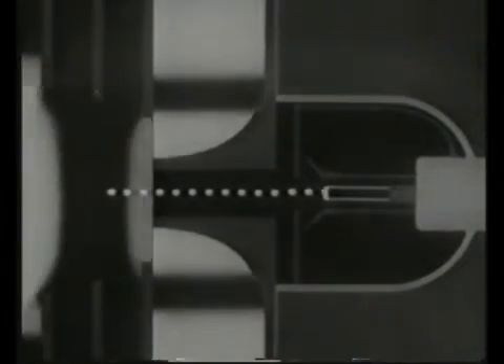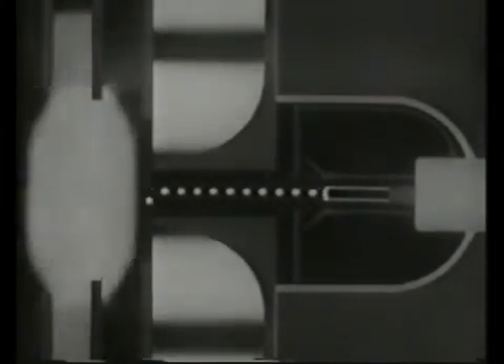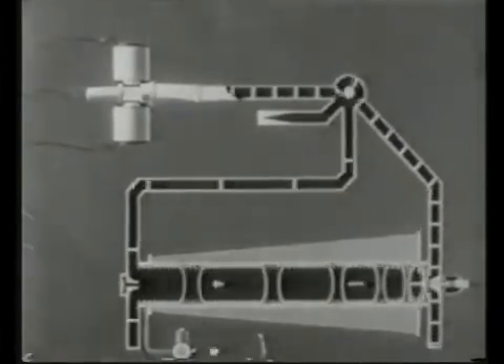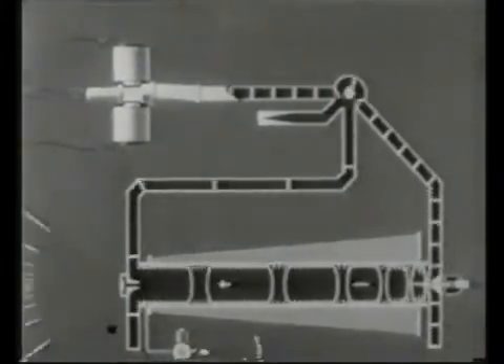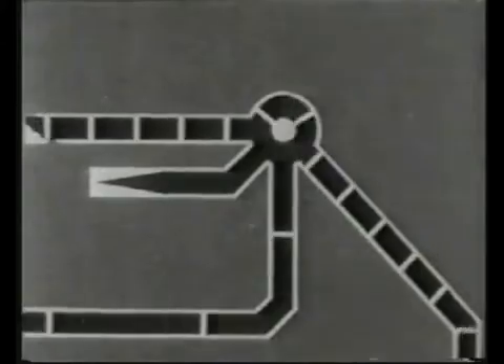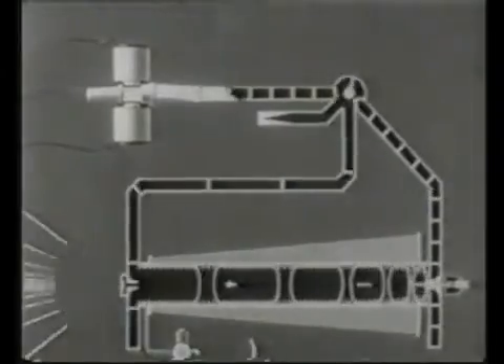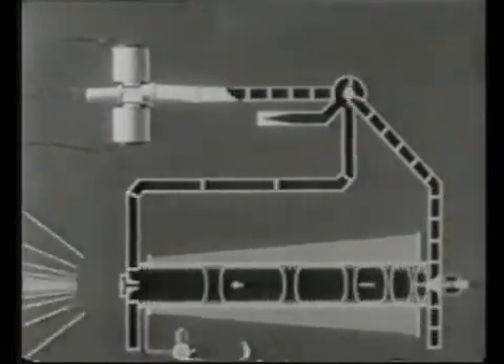Those which are injected into a retarding field will be rejected and lost. Those which are injected into an accelerating field will bunch together and continue to gain energy from the HF wave. So, finally, groups of electrons will strike the target at a speed of 99.95% c, and hard X-rays will radiate from it. The surplus HF energy is fed back from the target end through a subsidiary waveguide to a device known as the rat race, and recirculated with the power from the magnetron. During its journey down the tube, each particle increases its mass 30 times.